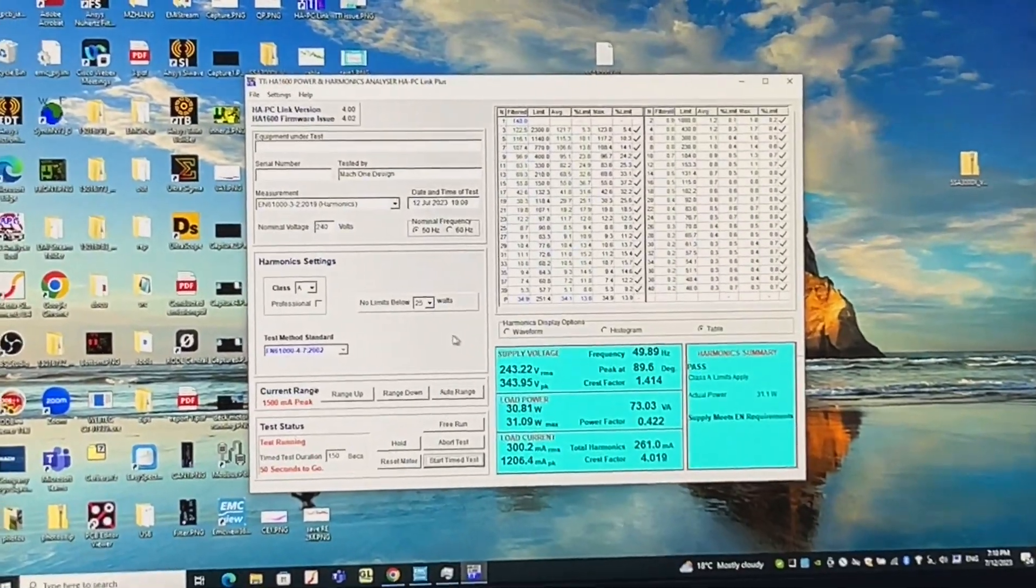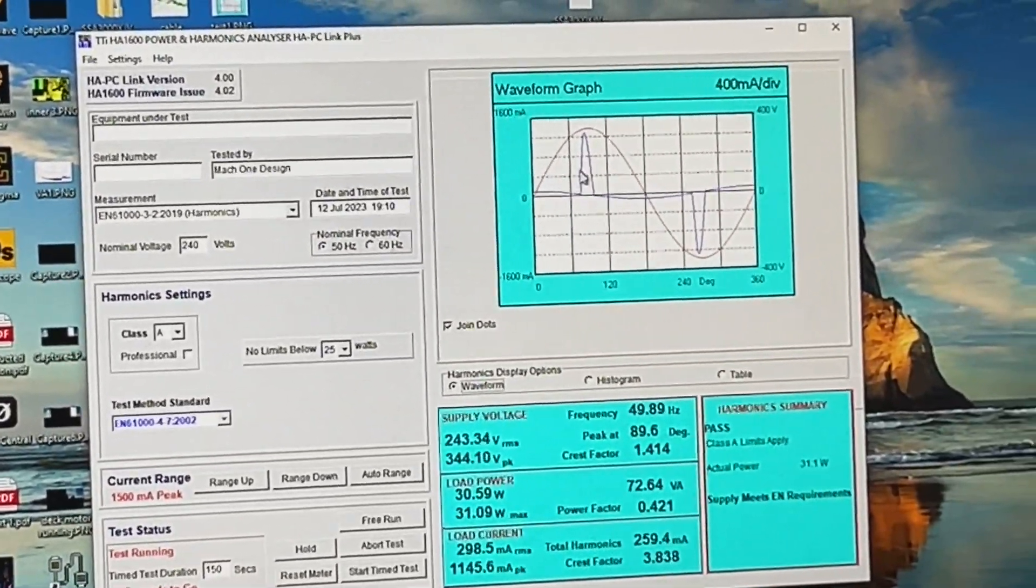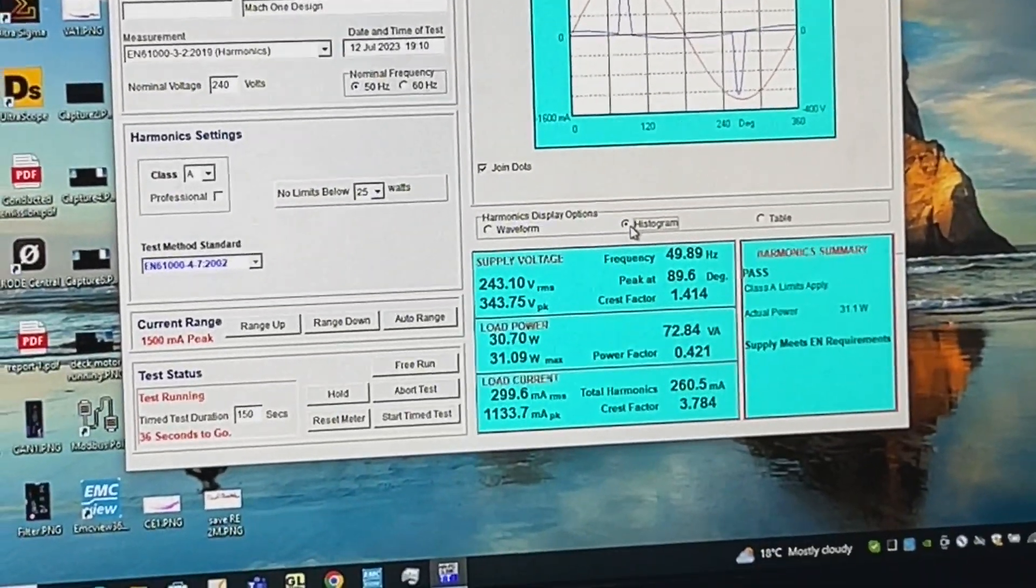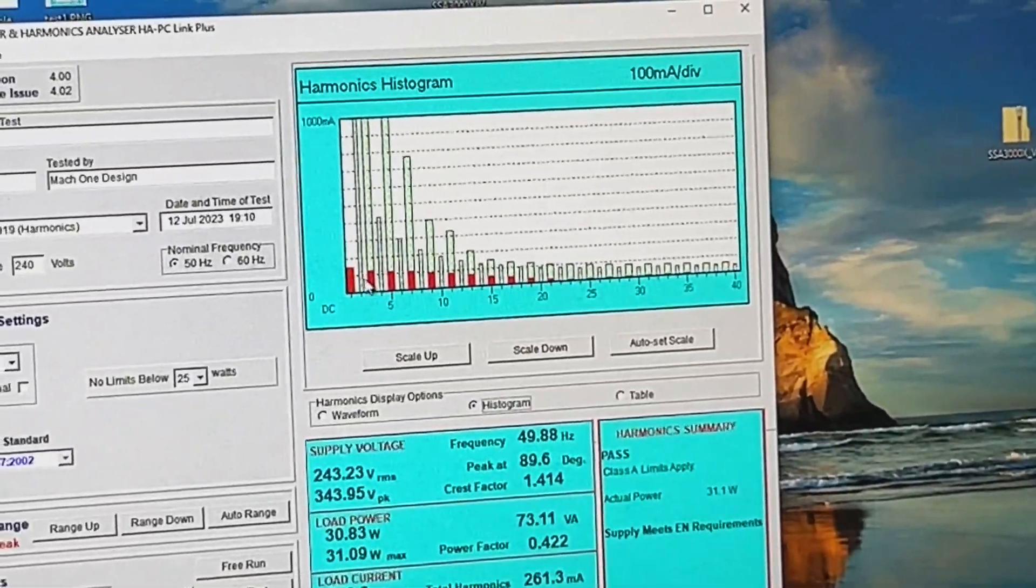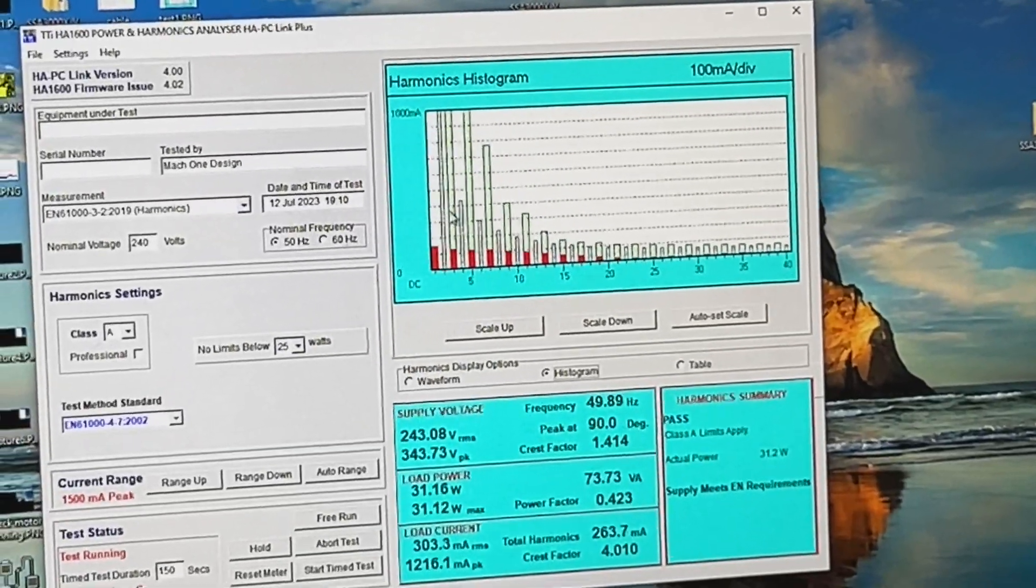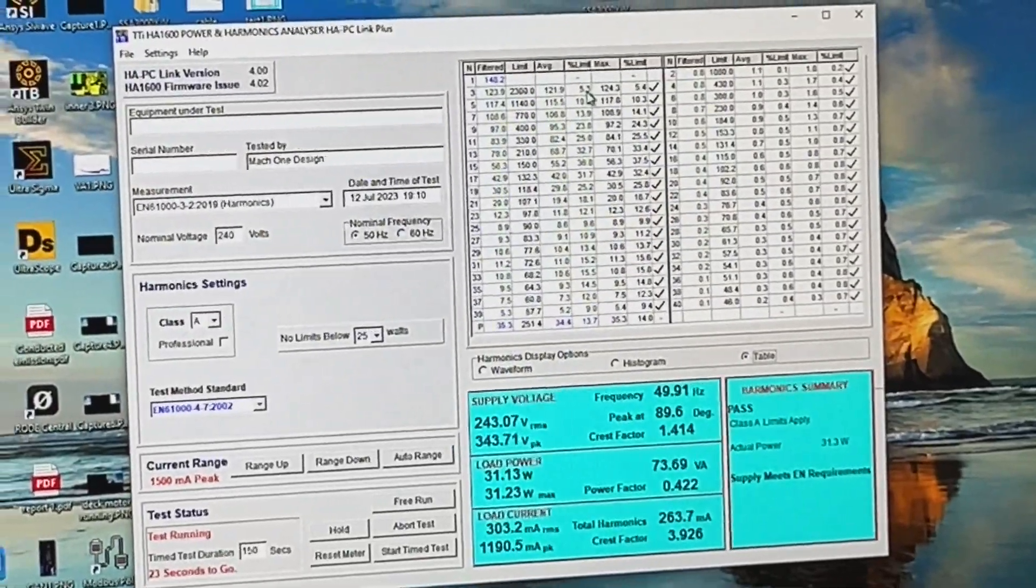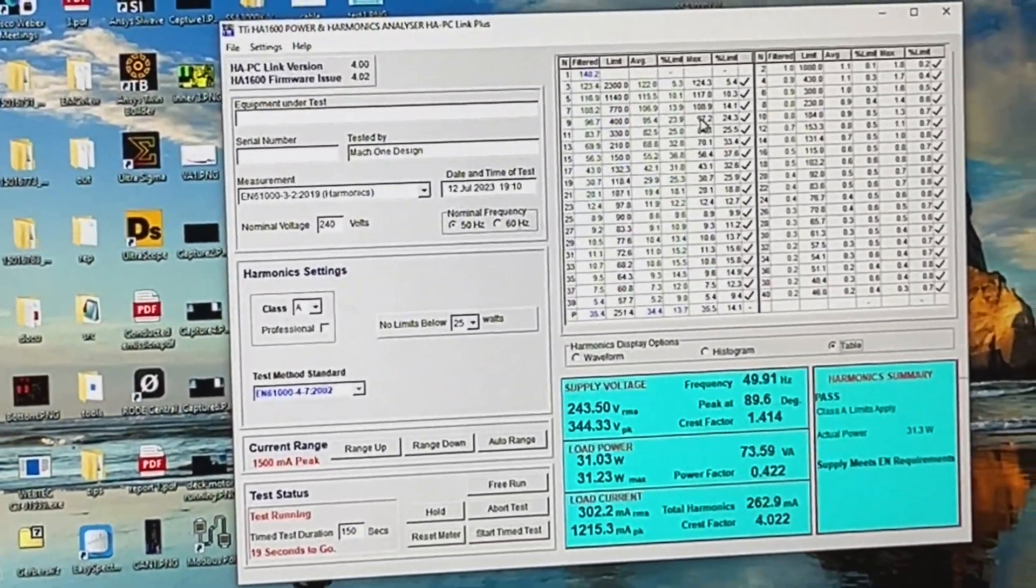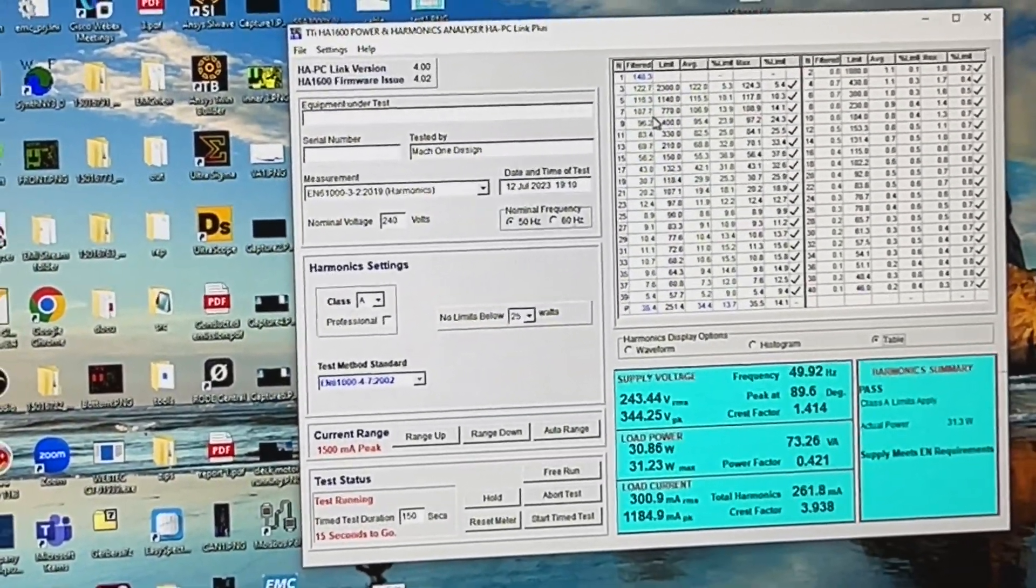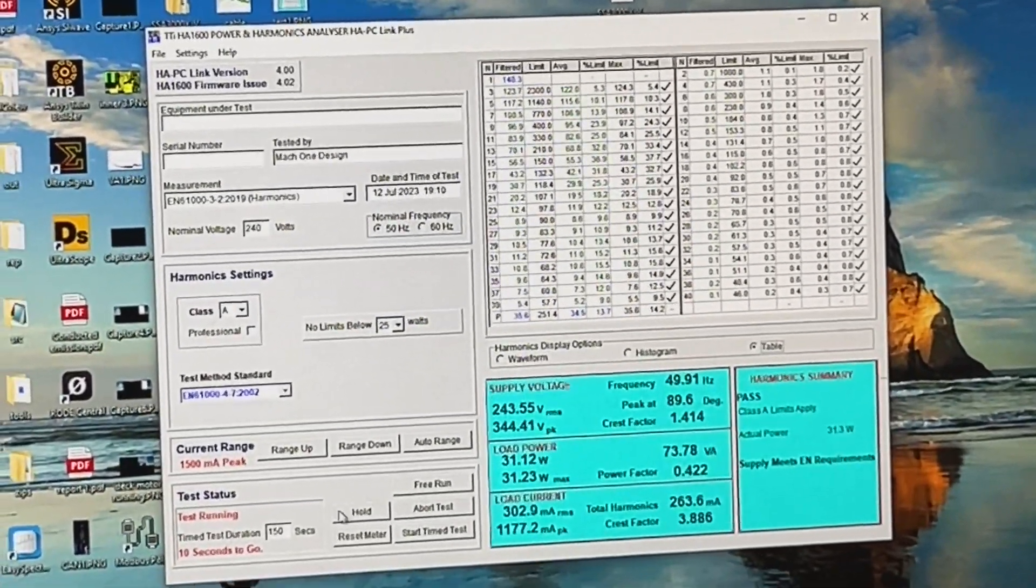The software also gives you a few different windows. So in this window is the waveform where you can see the current and voltage. In this case is the histogram diagram shows you the limit and whether your certain harmonics are exceeding the limits or in this case under the limits. You can also view in this table view where if you are familiar with the standard test reports often they give you a table view telling you the harmonics content and whether they pass or fail defined in the standards.